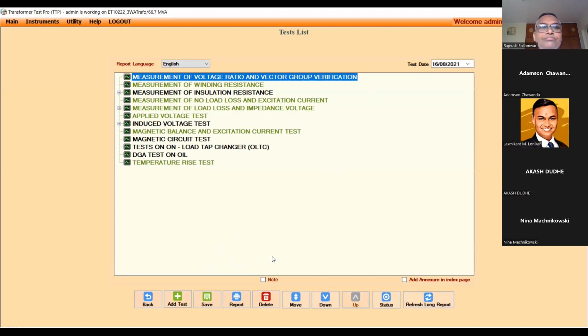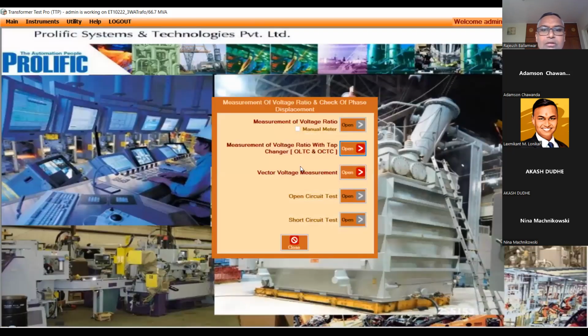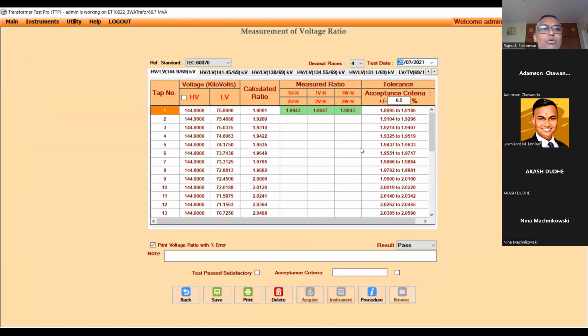It's going to open. First time it takes a little while, but then it is very simple. Here, measurement of voltage ratio with tap changer, OCTC, OLTC. I click on this, open. And then that's where the screen has come now. You can see the reference standard. Here you have a choice for each test, whether you would like to have a very different reference standard chosen. Decimal places, as has been seen earlier, you further have a facility to change it here, the test date.